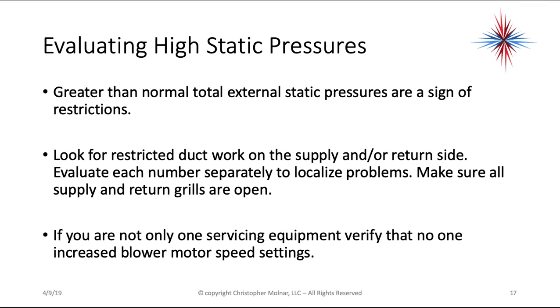High static pressure is another problem. Greater than normal total external static pressures are a sign of restrictions. Look for restricted ductwork on the supply or return side, and evaluate each number separately to localize problems. Make sure all supply and return grills are open. If you are not the only one servicing this equipment, verify that nobody has increased blower speed settings or replaced the blower motor with an incorrect model — this happens occasionally.